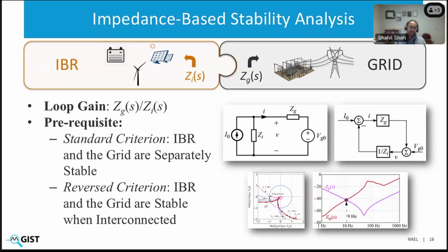So to do this stability analysis using these impedance responses, we plot either the Nyquist plot of the impedance ratio of grid impedance to IBR impedance, or we just compare the impedance responses. There are two different forms of impedance-based stability analysis. The standard criterion is one in which we assume that IBR and grid are separately stable, or these puzzle pieces are separately stable. What happens to the stability when you connect them to each other?